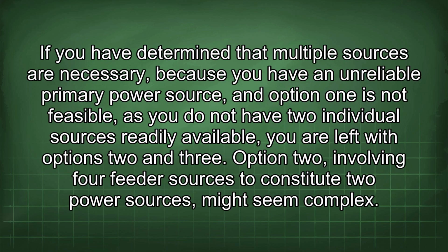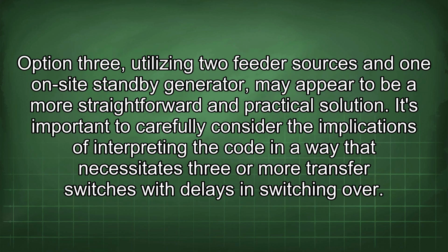If you have determined that multiple sources are necessary because you have an unreliable primary power source, and option 1 is not feasible, as you do not have two individual sources readily available, you are left with options 2 and 3. Option 2, involving 4 feeder sources that constitute 2 power sources, might seem complex. Option 3, utilizing 2 feeder sources and 1 on-site standby generator, may appear to be a more straightforward and practical solution.